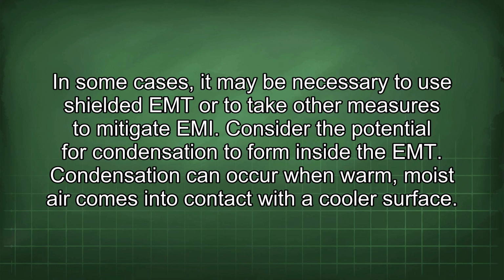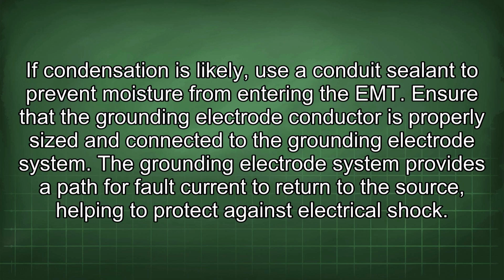Consider the potential for condensation to form inside the EMT. Condensation can occur when warm, moist air comes into contact with a cooler surface. If condensation is likely, use a conduit sealant to prevent moisture from entering the EMT.